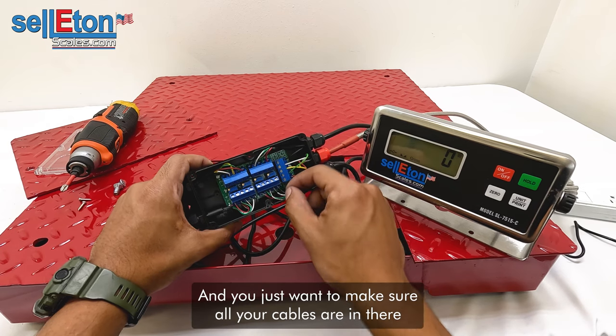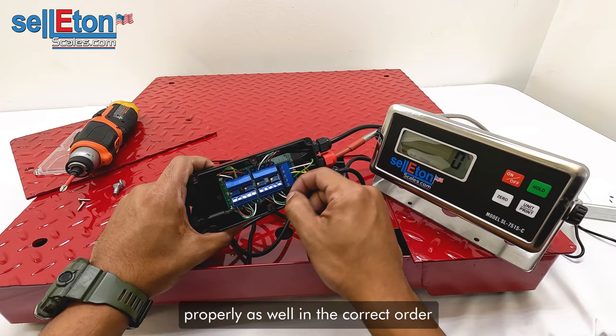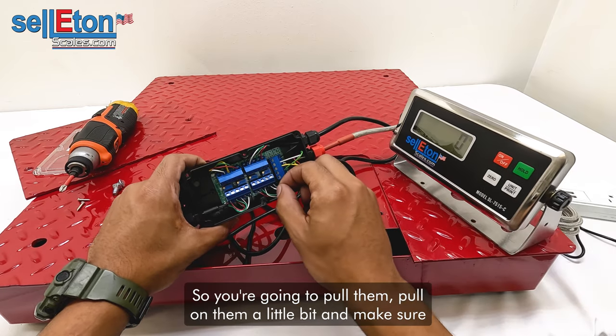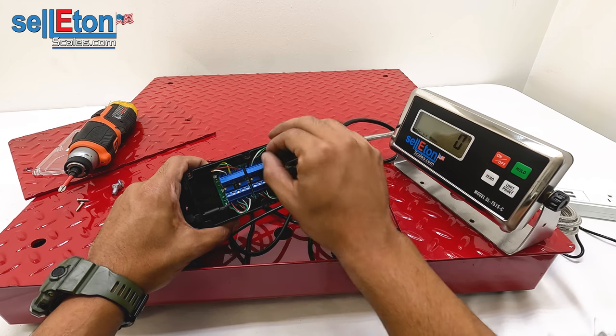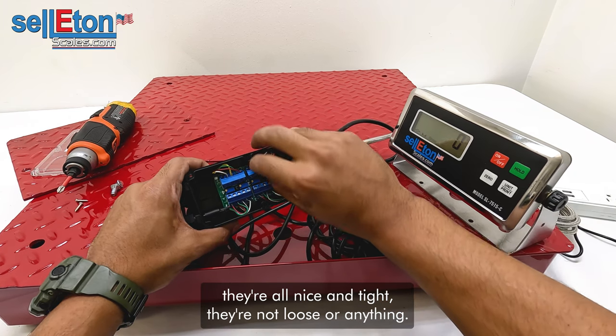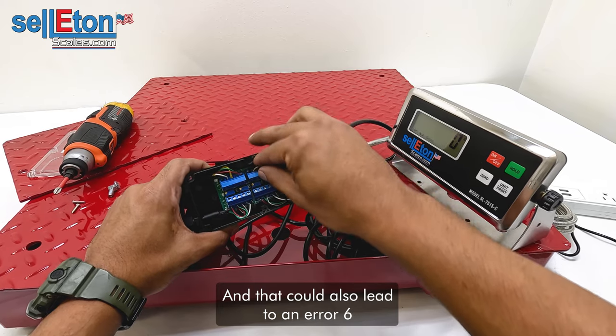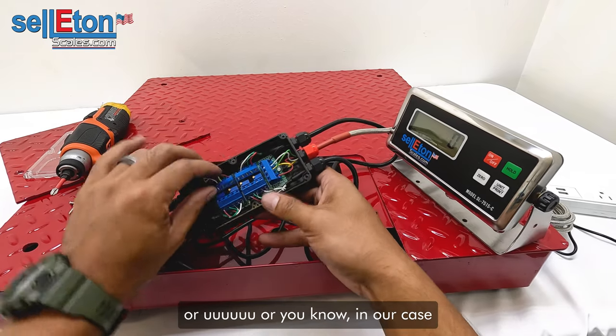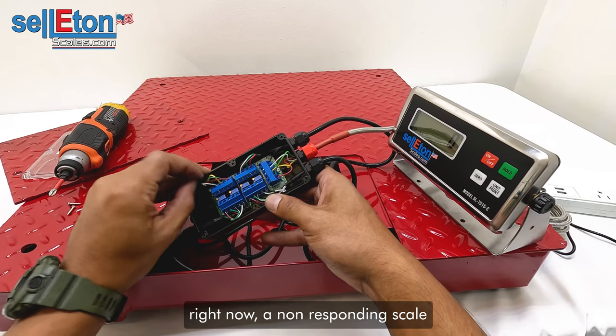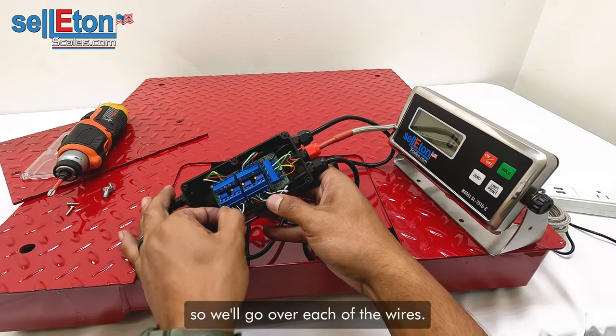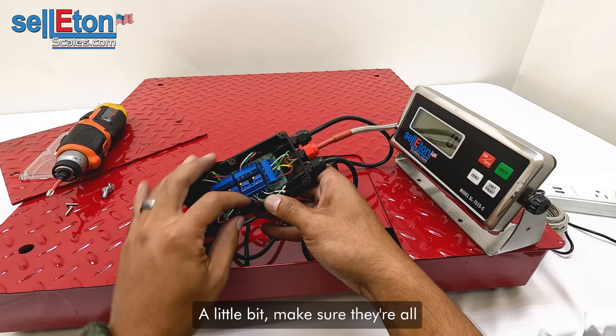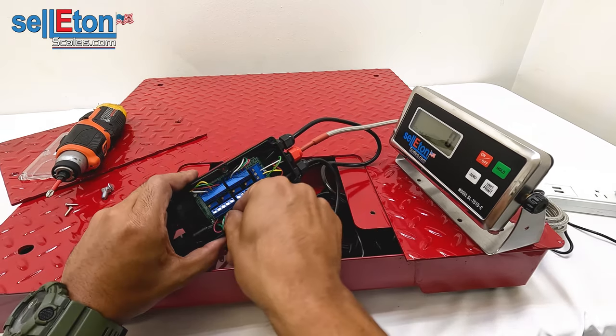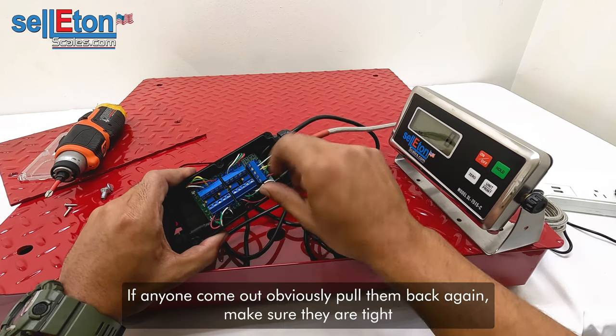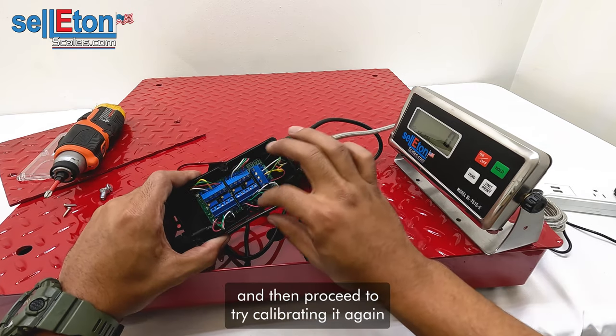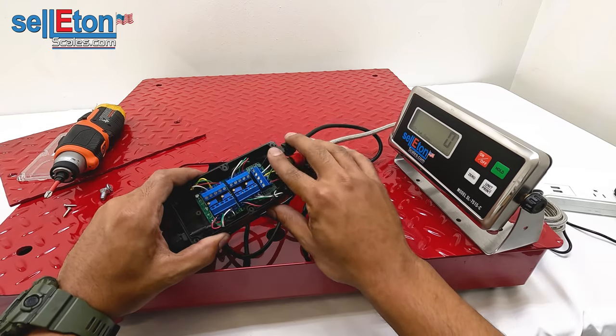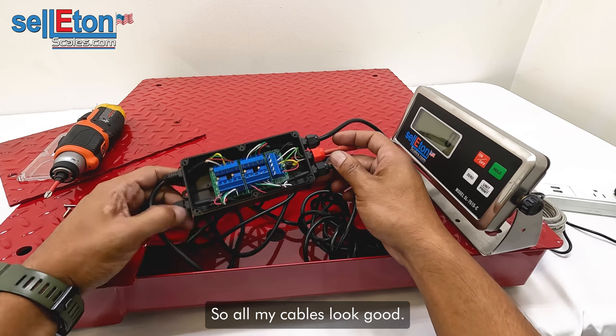And you just want to make sure all your cables are in there properly, in the correct order, as well as snug. So you're going to pull on them a little bit and make sure they're all nice and tight, not loose or anything. That could also lead to an error 6 or, in our case right now, a non-responding scale. So we'll go over each of the wires and pull on them a little bit. If any of them come out, obviously put them back in, make sure they're tight, and then proceed to try calibrating it again. And we'll see if that works. So all my cables look good.